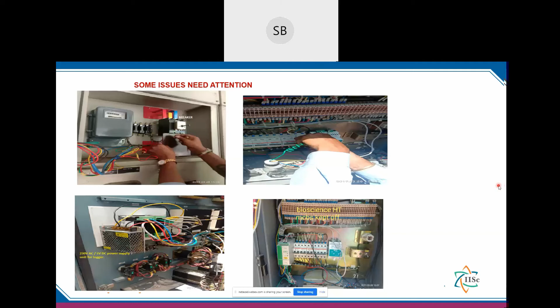We ensure the information is fed as minute data from each of the departments to the center, the monitoring station. One thing I forgot: wherever the distribution box earlier had meters, an ammeter or voltmeter, our smart meter is placed in the same location where the earlier ammeter was. So we just remove the ammeter and fix the smart meter in that junction. This is the data logger, and this is the SMPS for the data logger. There are some minor issues that do crop up, and we take care of these things.